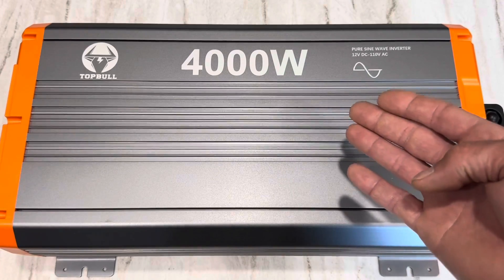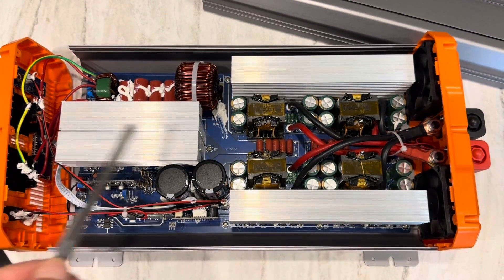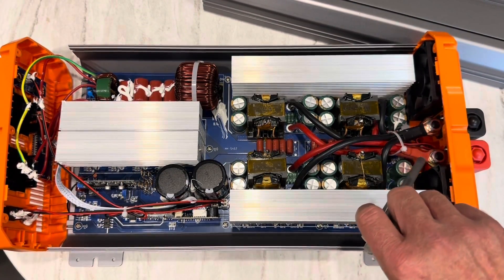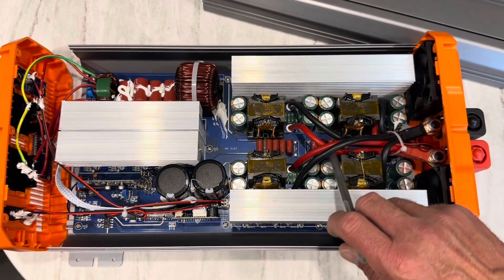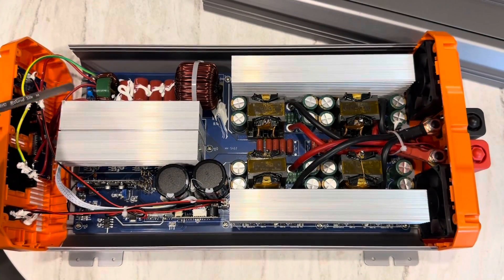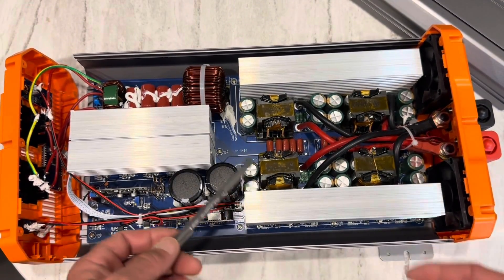Want to see the internal construction and build quality on this unit? Of course you do. I'll take the screws out and open it up. A few screws in the front let you drop the cover down and slide the top cover out — I wouldn't recommend doing that on a warrantied unit, but this one's a test rig. On the DC side, coming in from the battery connections, the bus bars come through the shell of the unit to four number-eight, 200-degree Celsius silicone jacketed wires with four 30-amp fuses, allowing up to 120 amps per leg.